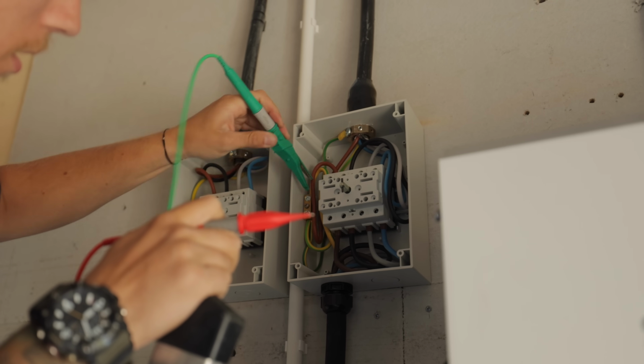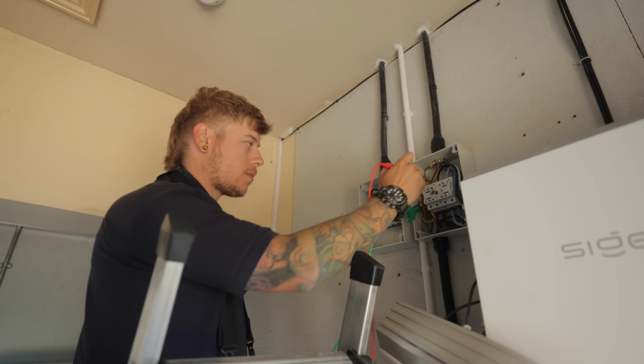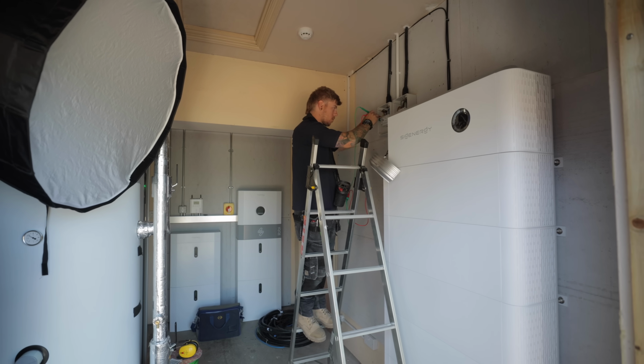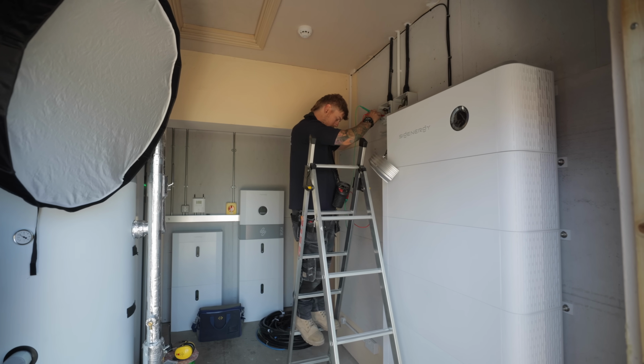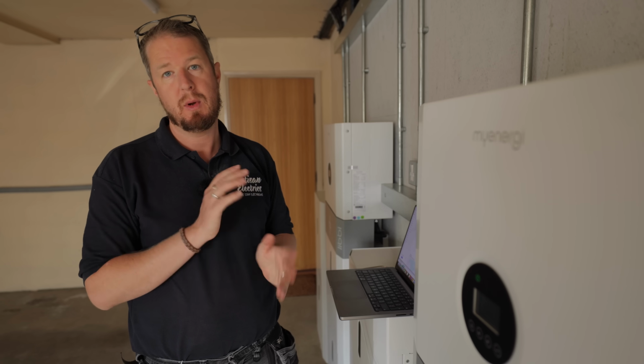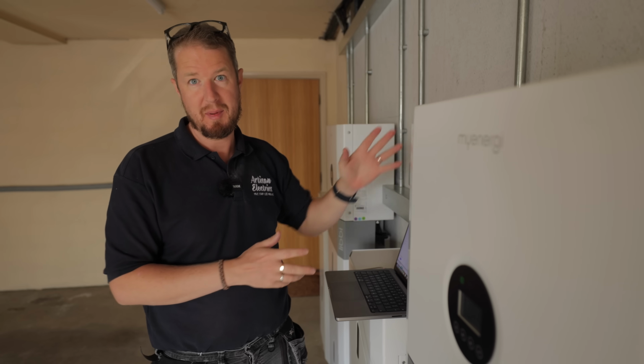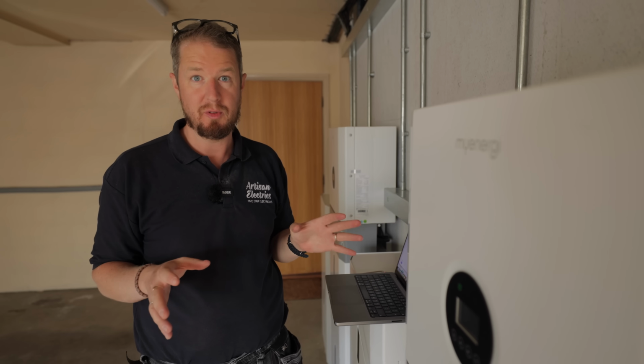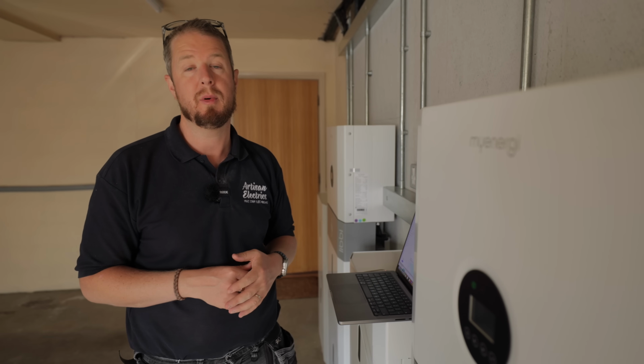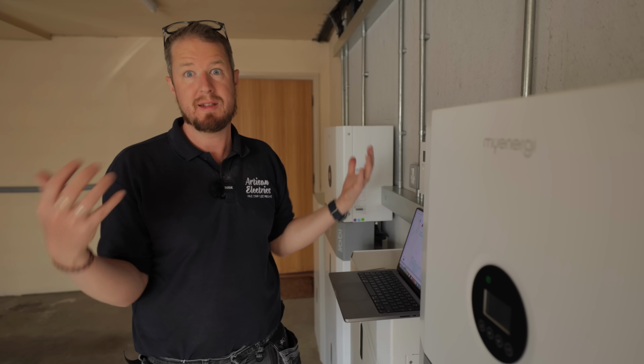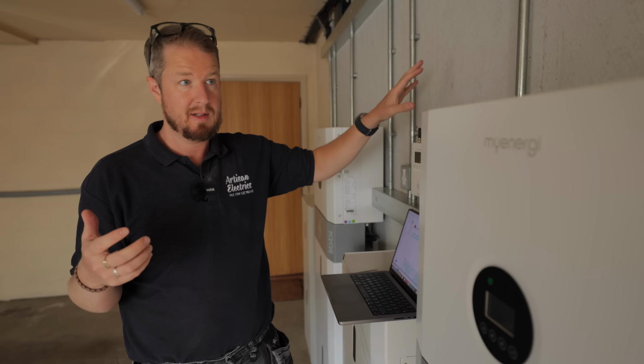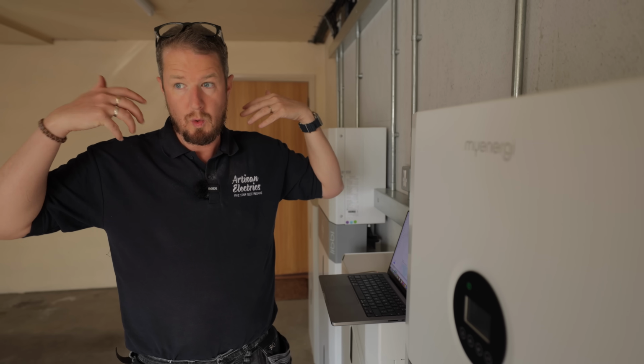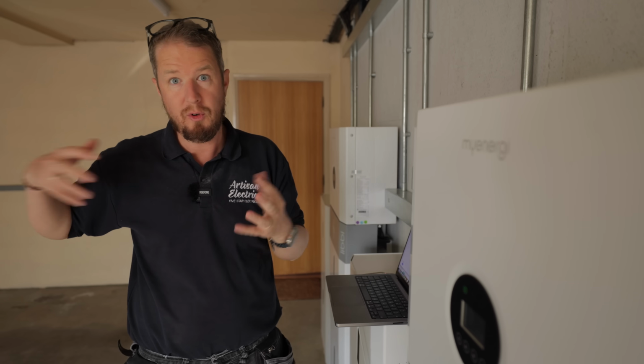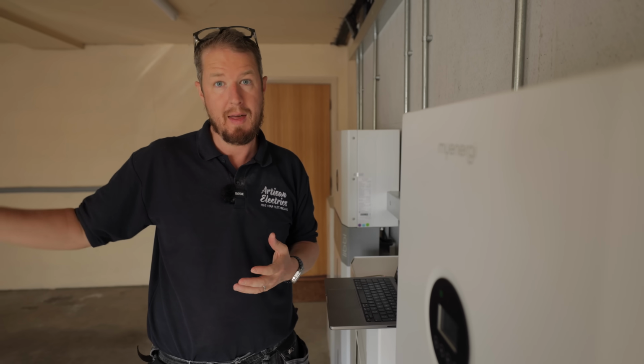So the fun part of these systems is often the planning. The fact that we've got existing battery systems here and existing solar inverters here means we can't just come along and slap in another big battery system. We have to get approval from the DNO, or distribution network operator, to increase the size of the system, essentially, because technically that Sigen battery system and these batteries here could all push power out and force discharge to the grid and affect the local grid.